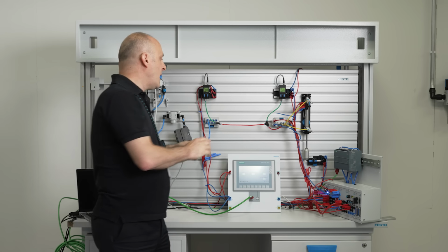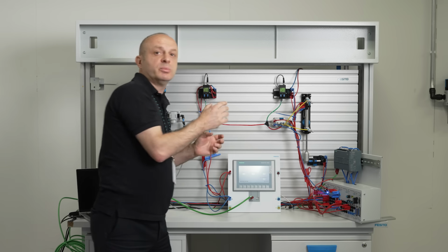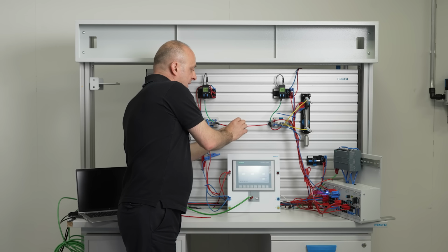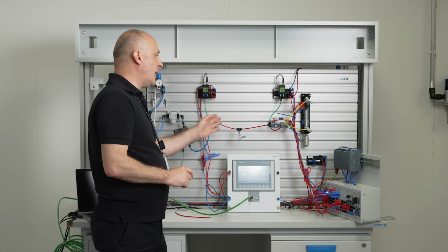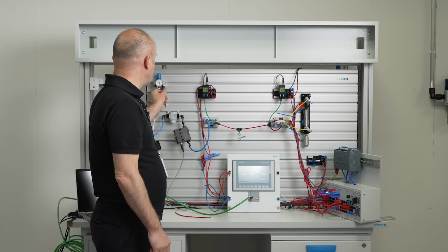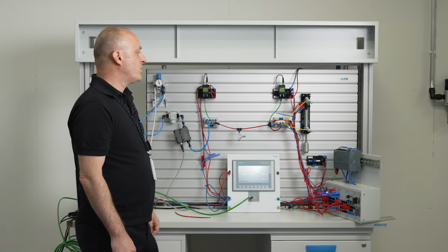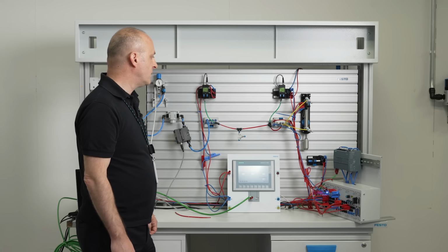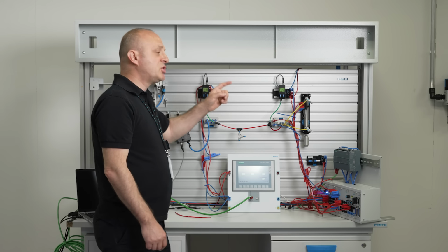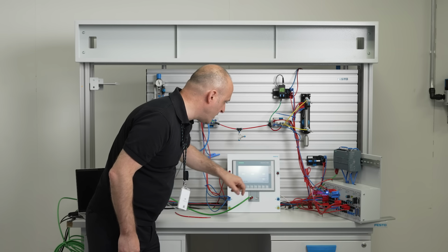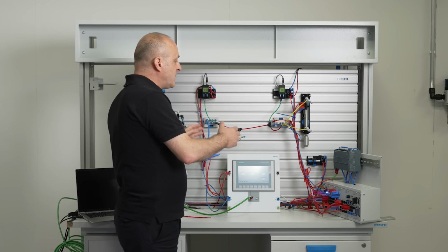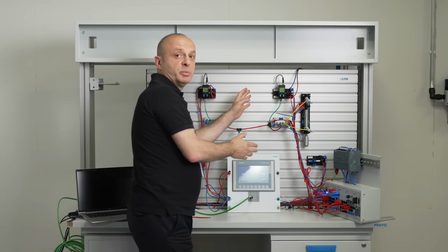Now I will replace this tube and create the leakage on the machine. Have a look at what happens with the leakage. Now we have the leakage on the compressed air line. We will see if we can provide enough pressure on our machine. I turn the air on. We have the leakage. Machine starts. It is working. And stop. The machine stops because we can't provide enough pressure. The pressure we provided was less than the adequate pressure, so the leakage on the line caused an issue on the machine.